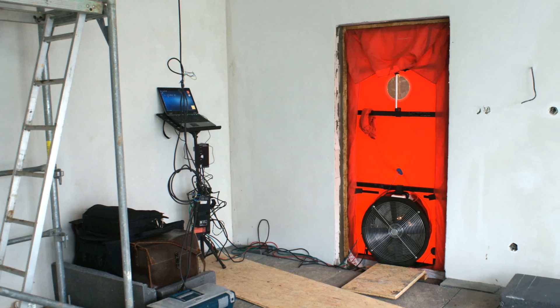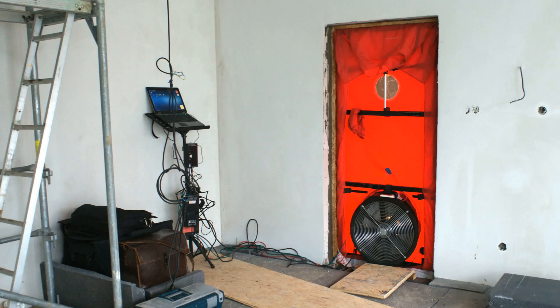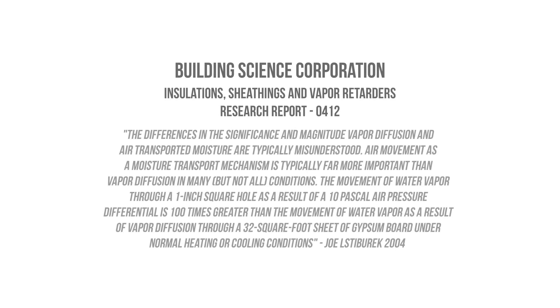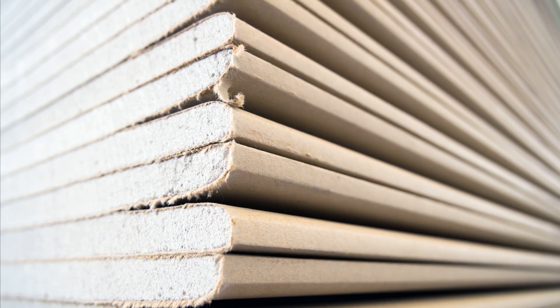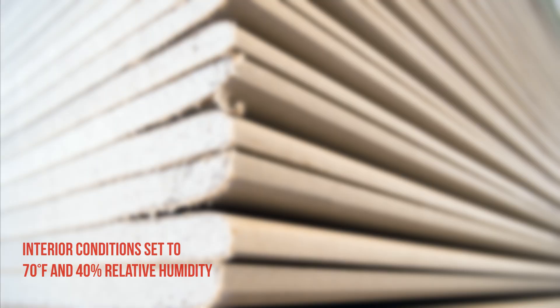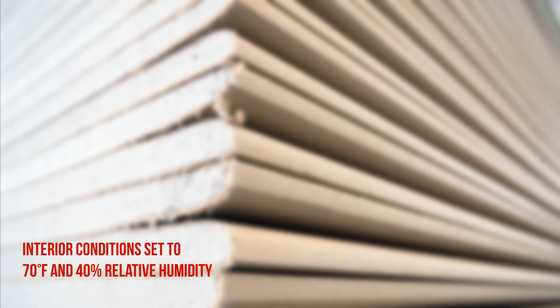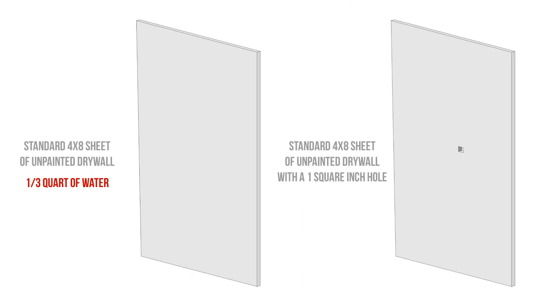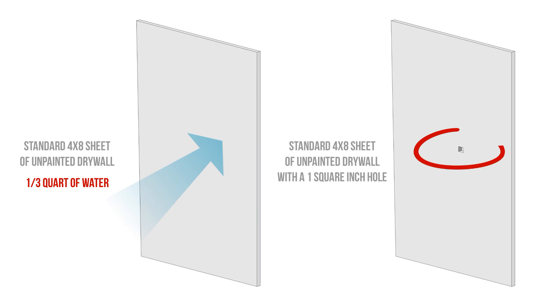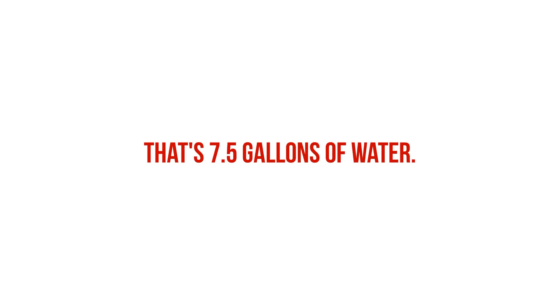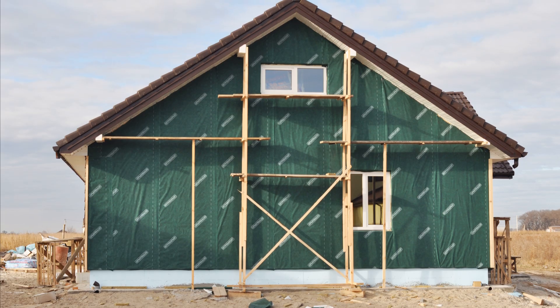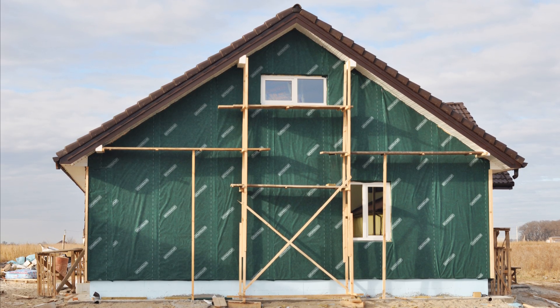Building Science Corporation tested this decades ago, which became the basis for modern-day codes in air leakage tests. They determined that air leakage had the potential to transport moisture in quantities that were orders of magnitude higher than diffusion during the same time period. The test was conducted on standard 4x8 sheets of drywall in a cold climate throughout an entire heating season, with the interior kept at 70°F and 40% relative humidity. The airtight sheet had about a third of a quart of water diffuse through it, while a sheet with a 1 square inch hole resulted in nearly 30 quarts of water transported through air leakage — 100 times more than diffusion, equivalent to 7.5 gallons of water through that single hole.